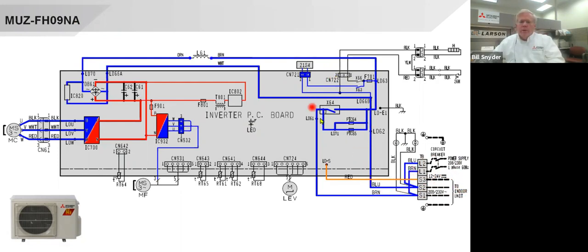We're coming in here. This is the noise filter section. Up here is the reactor. And here is where we convert it to DC voltage. It's 300 volts DC downstream to this. In this case, we have the IC, which is the power module or inverter circuit.